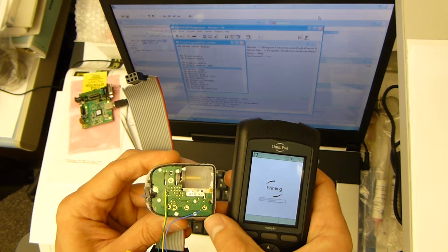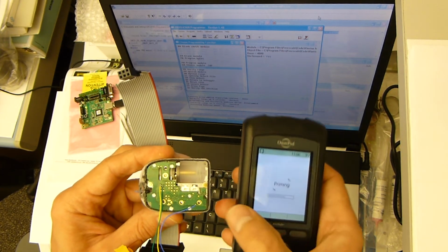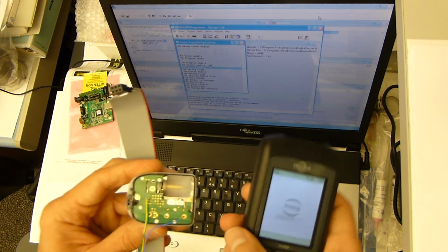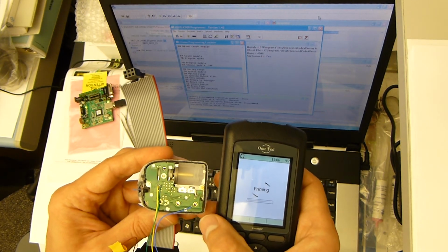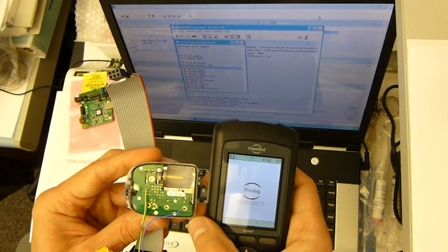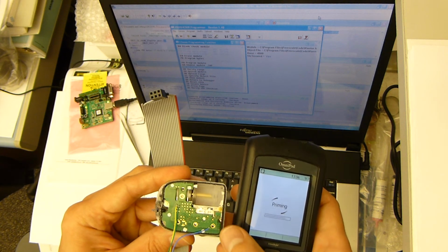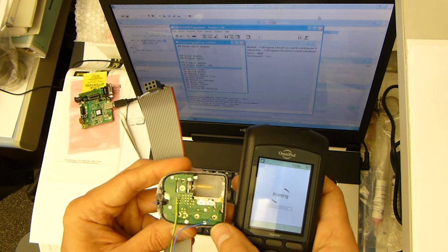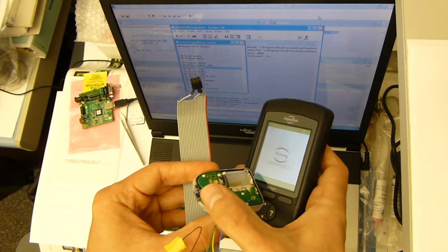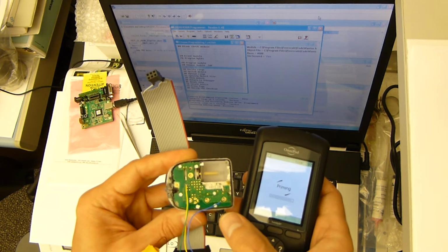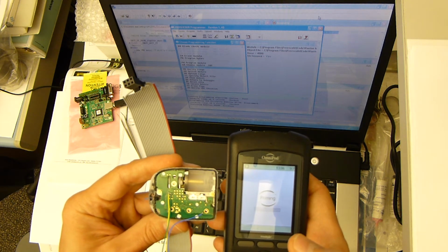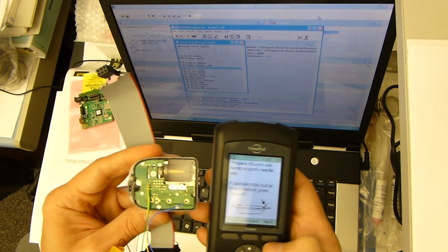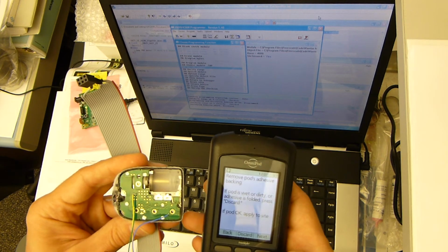And at the end of the priming process, the PDM and the pod are linked together so that they can securely communicate with each other. So a few more seconds to finish the priming. So now the gears stop turning and you can see the few drops of insulin pushed out of the tank. Okay, what's next?